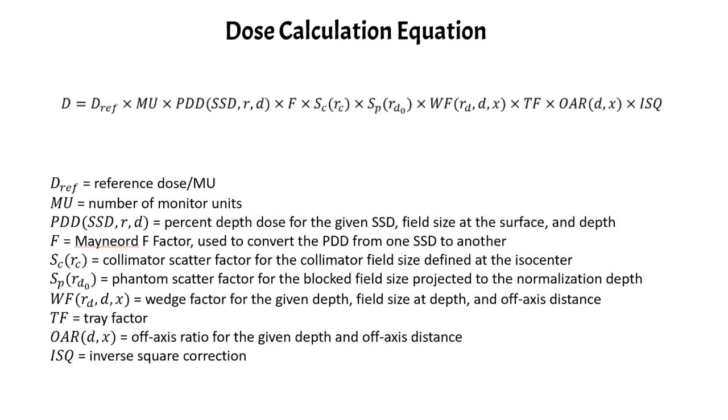F is your Mayneord F factor, which is used to convert the PDD from one SSD to another. This is usually equal to one if your setup SSD is equal to the same SSD that was used to measure the PDD.